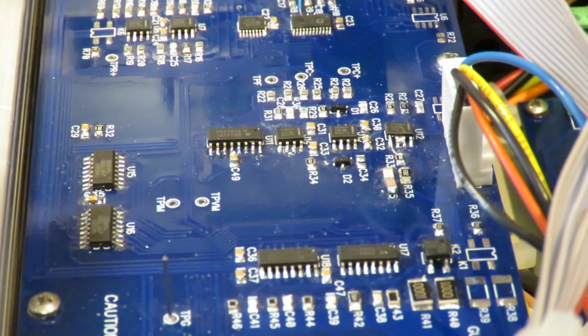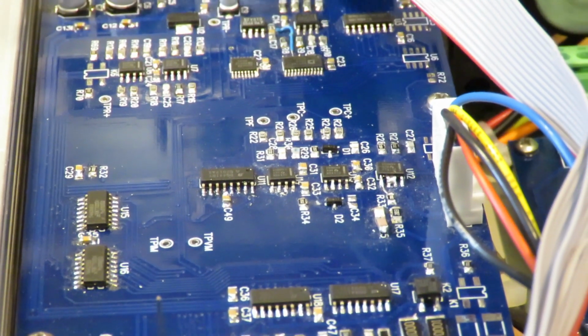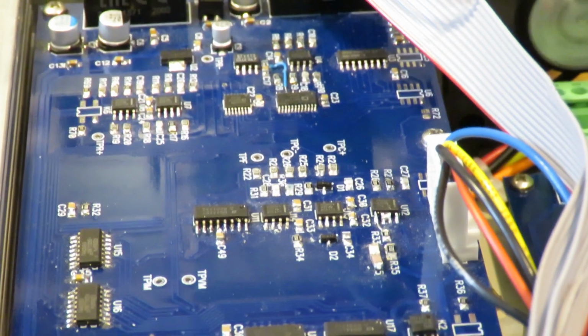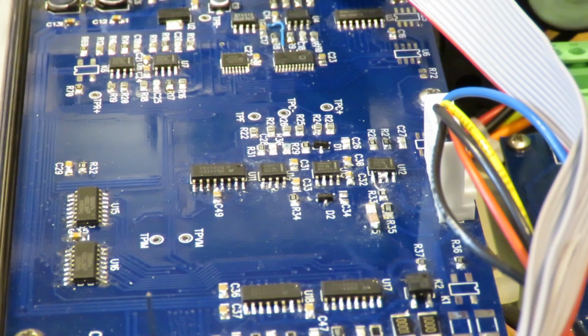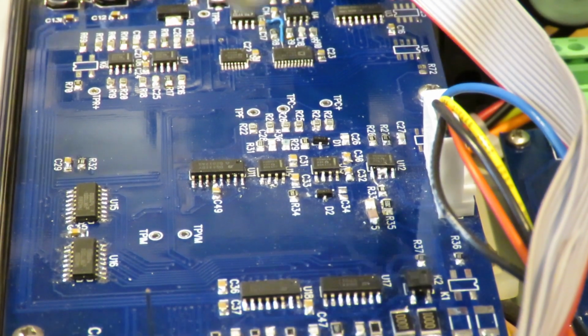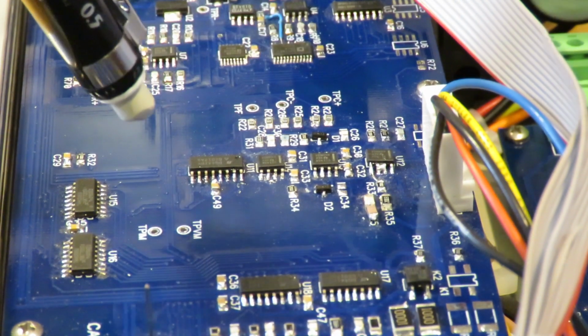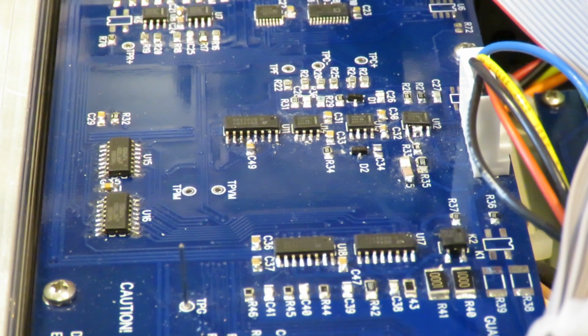This next section here is the crossover. That's what does the automatic switching between current and voltage control. And it provides the clamps, the current and voltage clamps. These 2 ICs are control registers that provide 16 bits of control. They set the current and the voltage ranges. They turn on remote sense, and they turn on and off the output, and they set the mode of the instrument.